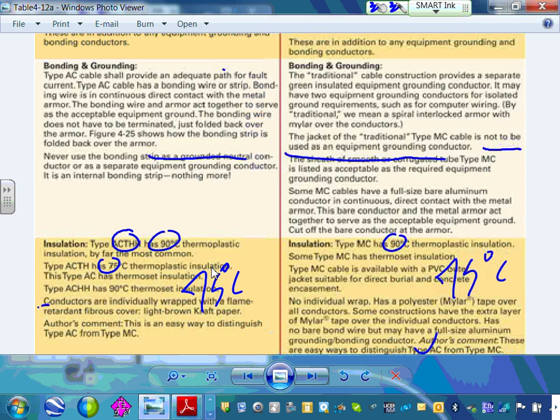Now, you're going to tell me, Chad, here's a conductor. If I don't know, guys, this is number 14. If I don't know which column to go to, number 14, AC or MC cable, have no idea where the lugs are, where's your default? Which column is it, 60-degree, 75 or 90? No derating. 60. 60 if you're not derating. If you're derating, then you can go to 90-degree.